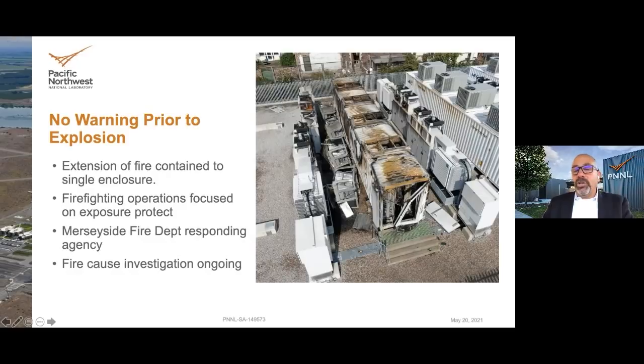So no deflagration venting, there was a clean agent system present. The fire department's actions were really focused on protecting the exposures, because when they got there, there was fire fully involved in this container. So they were protecting the inverters and the neighboring container. Again, these comments are based on just a fire department response report, not a fire cause investigation, which is still underway.